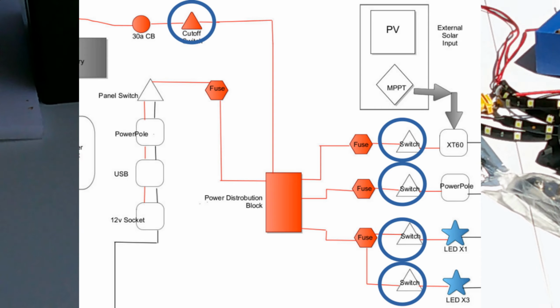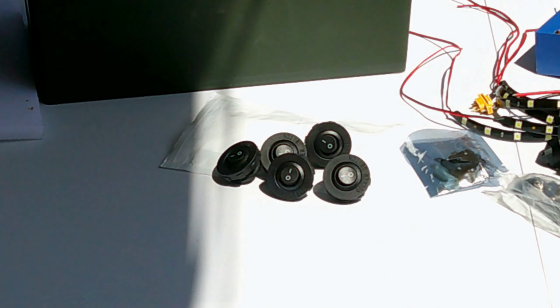We've got a total of 5 rocker switches. These are simple on-off, single pole, single throw switches. One of them will be used for the main cutoff switch that goes between the circuit breaker and the load distribution panel. The positive lead comes from the battery, goes through the circuit breaker first, then to the switch, and then to the load center of the load distribution panel. So one of those will be used for that.